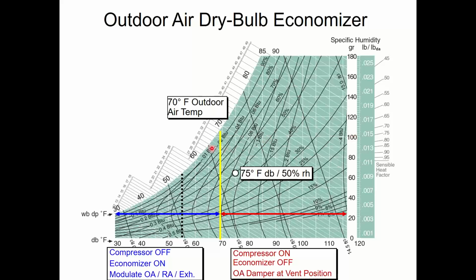If you suck in air right where my red dot is, it's going to cause a humidity complaint in the building. I promise you. I refer to this space right here as the triangle of death. If you take that air in on an economizer day, people are not going to be happy with you. That triangle over here was not a problem because it wasn't a lot of real moisture. It was a high percentage, but not a lot of real moisture. Up here, it's a problem. So avoid the triangle of death.